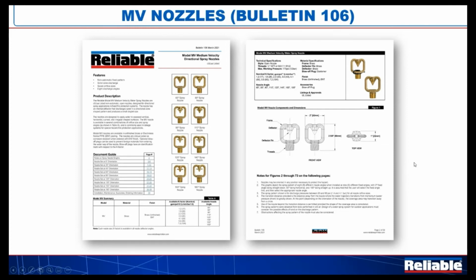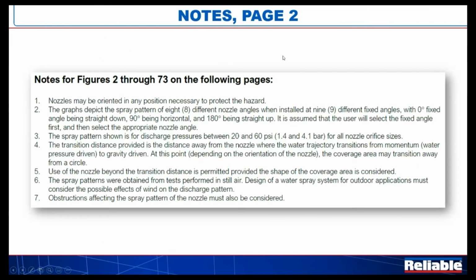I would like to point your attention to the notes at the bottom of page 2 and look at a couple of those real quick. Number 1, as I mentioned, these nozzles can be oriented in any position. Number 2, we just talked about. The spray pattern shown is for discharge pressures between 20 and 60. So between 20 and 60, medium velocity, if that's what you want to call it, the cone shape stays pretty stable. Now over 60, the cone shape may start collapsing a little bit. Under 20, we may not get the kind of breakup of water that we're looking for. So we're in that 20 to 60 psi range.